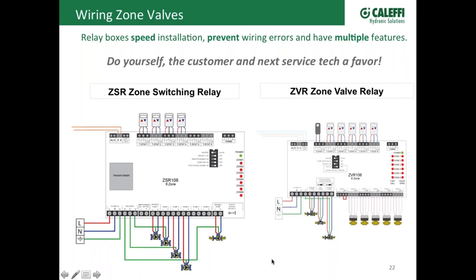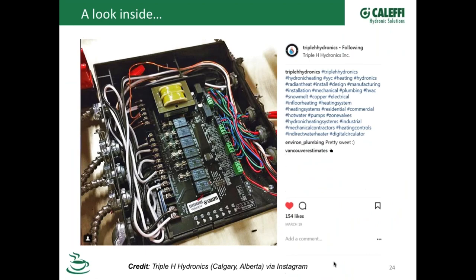So I think we came up with a lot of really unique features, and thanks to the people out there asking us, and here's a classic example, one that was installed. A lot of the features that you see in this box are because you told us that's what you wanted or needed out there. So the status, the priority, having the color-coded connections up here so you get your different thermostats on the right ones, nice screws on there instead of push tabs so you can get your wire in there, make sure you've got a good connection on the top and bottom. Multiple grounds, so you don't have to put a wire nut in there and twist all your green wires together. So if you haven't tried one of the Caleffi boxes, I think you're really gonna be impressed with what we did inside there.